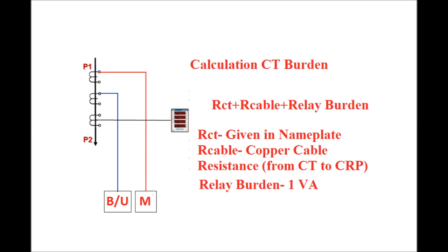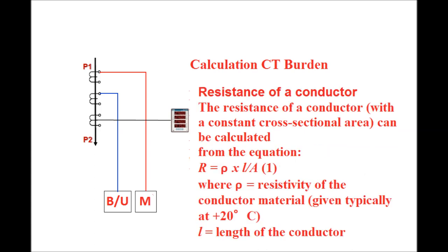In the CT secondary side, we have the CT secondary coil resistance, the cable connected from the CT secondary side to the CRP panel, and the relay burden. RCT is the CT secondary resistance given on the nameplate. R_cable is the resistance of the copper cable connected in the secondary side of the CT to the control panel. The relay burden is normally a maximum of 1 VA. This is the CT secondary burden.